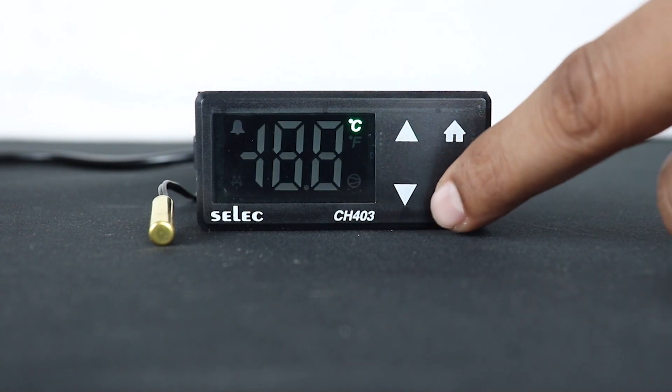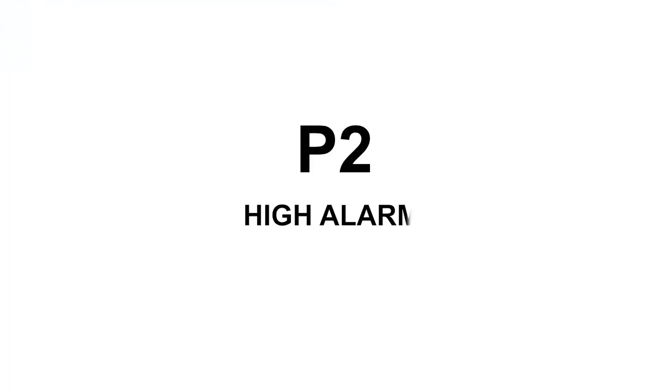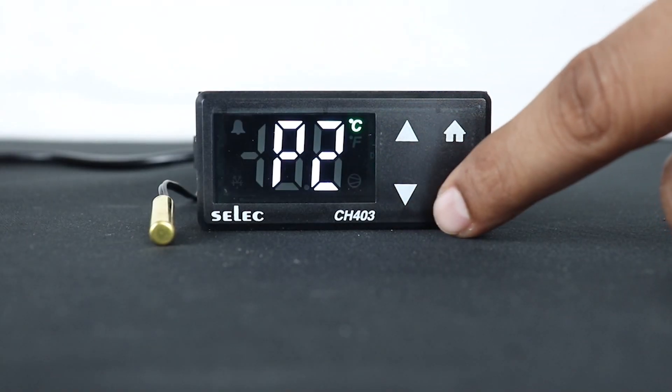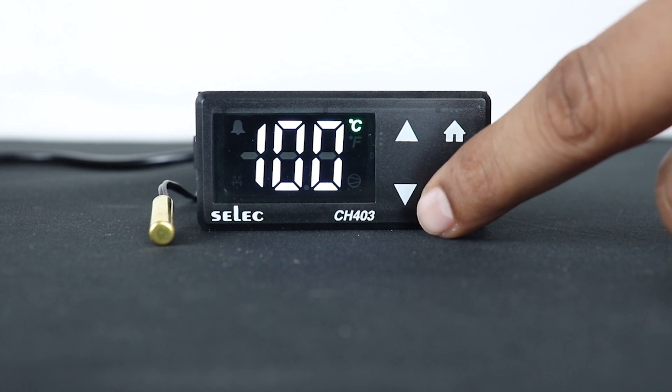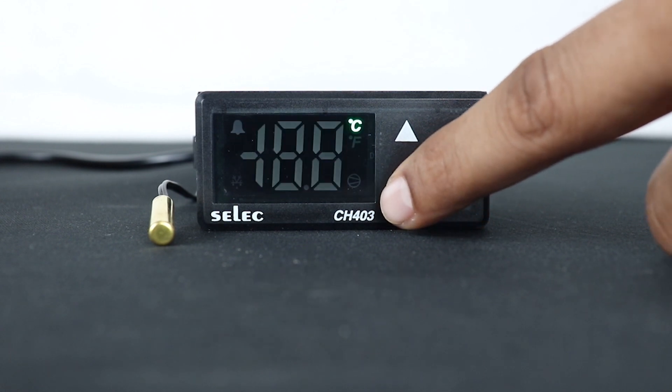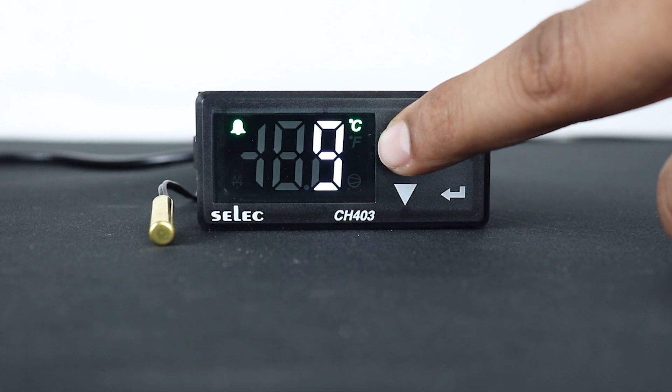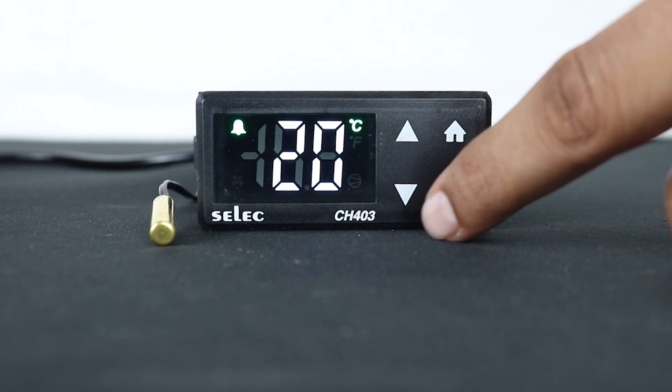To save the control mode, press the enter key once to the next parameter, that is P2 which denotes high alarm. Press the enter key to edit, up and down keys to increment and decrement the value respectively. Here we are taking 20 degree Celsius temperature as high alarm. To save the value, press enter key once.